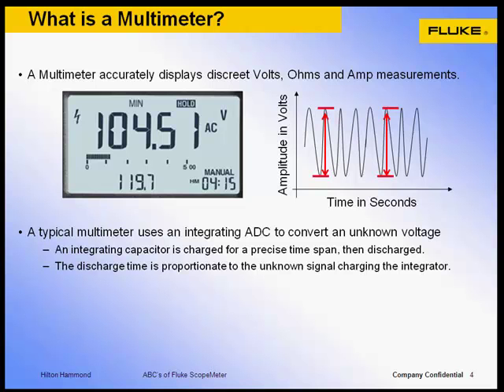Next, the circuit will discharge the capacitor using a reference voltage of opposite polarity until it reaches zero volts. The discharge time is precisely measured by a microprocessor clock. The time it takes to discharge the capacitor is directly proportional to the unknown input signal level. The longer the integration or deintegration time, the higher the resolution and the greater the accuracy.